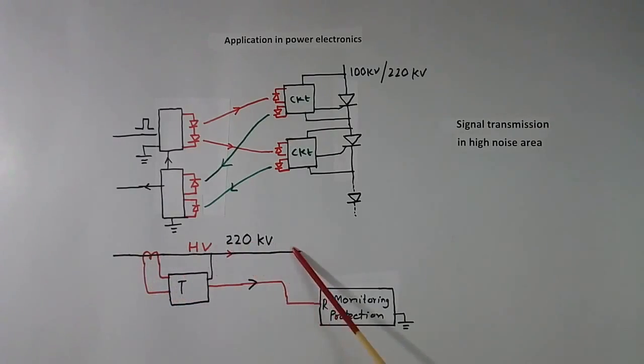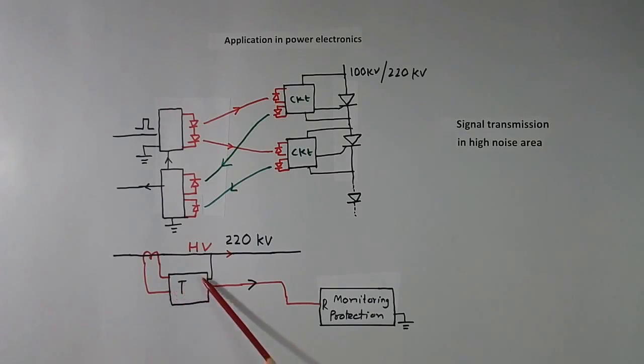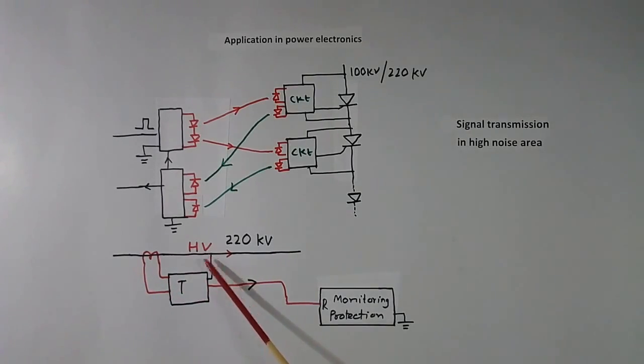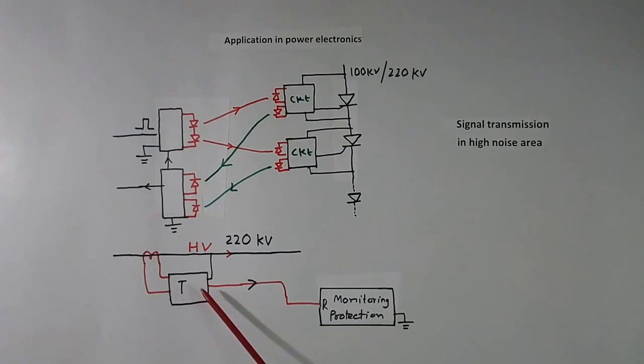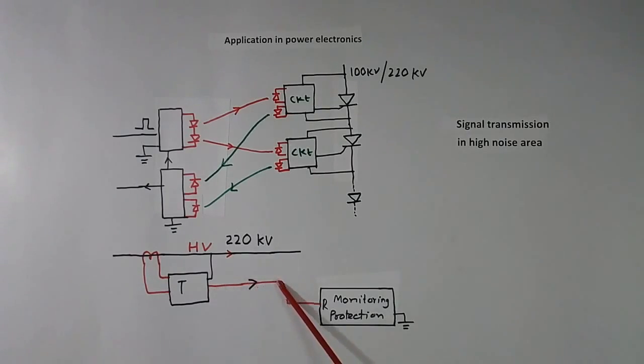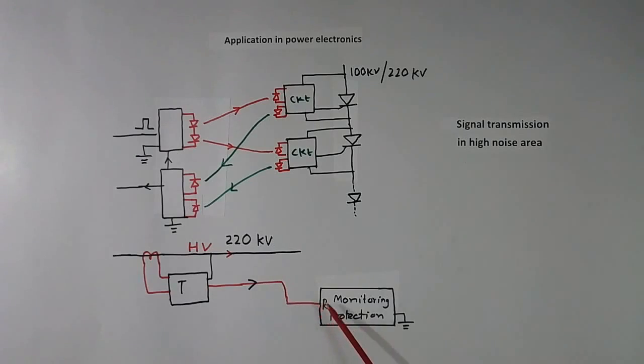Here we have 220 KV, and a CT is connected. There is a circuit here which is connected to the 220 KV line. This electronic circuit measures the current or any other parameter we want, and then converts the electrical signal to an optical signal via fiber optic cable. We receive the optical signal here, convert it into an electrical signal, and use it for monitoring or protection.